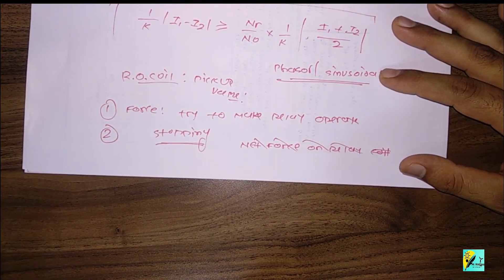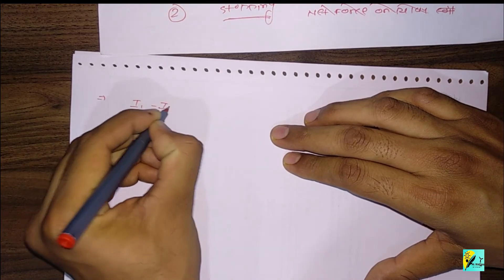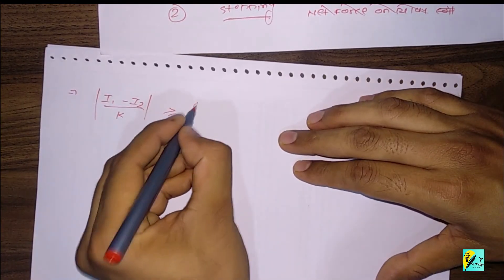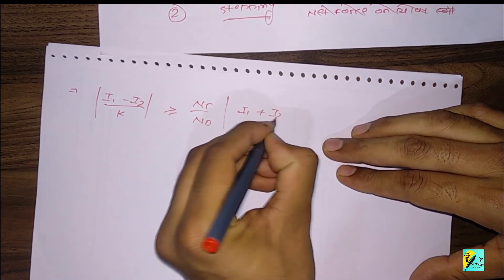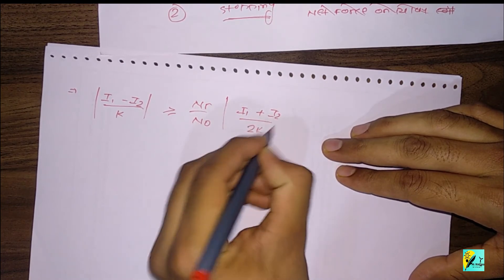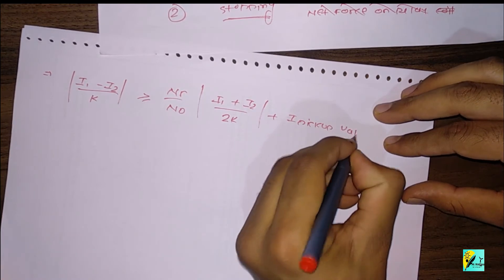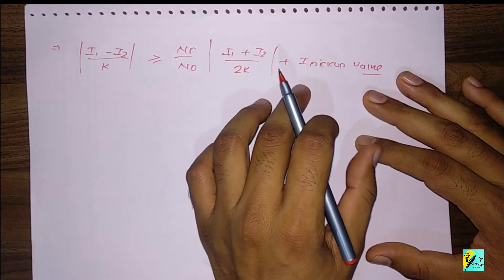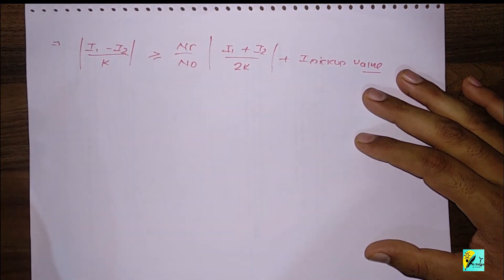So the net force on the relay coil should be more than the pickup value, and then the relay may get operate. We can write: (I1 minus I2)/k should be greater than (Nr/N0) multiplied by (I1 plus I2)/(2k) plus I_pickup. The operating force should be more than the restraining force by an amount equal to the pickup value.